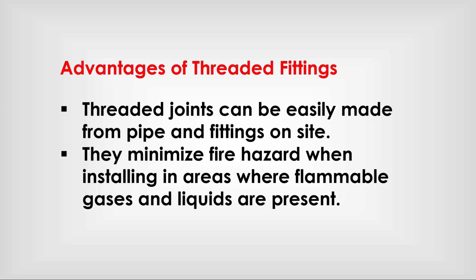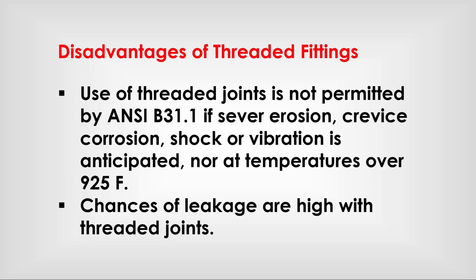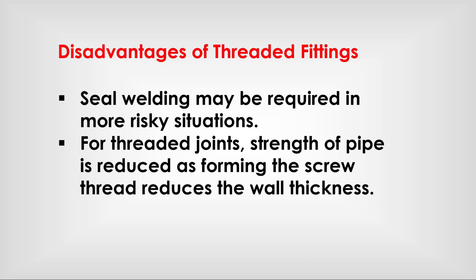Advantages of threaded fittings: threaded joints can be easily made from pipe and fittings on site; they minimize fire hazard when installing in areas where flammable gases and liquids are present. Disadvantages: use of threaded joints is not permitted by ASME B 31.1 if severe erosion, crevice corrosion, shock, or vibration is anticipated; nor at temperatures over 925°F; chances of leakage are high; seal welding may be required in more risky situations; threading reduces the wall thickness of the pipe.